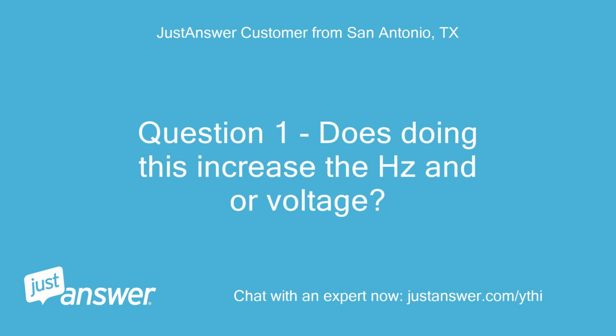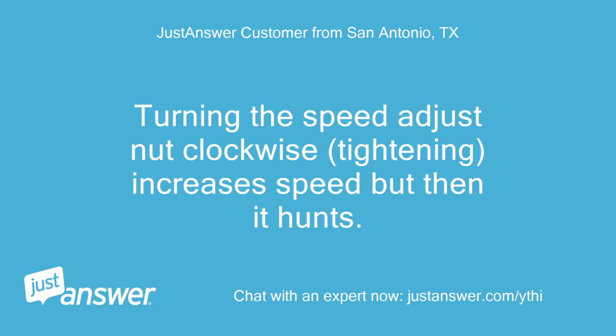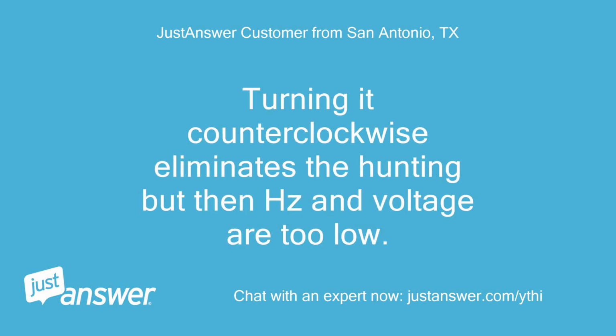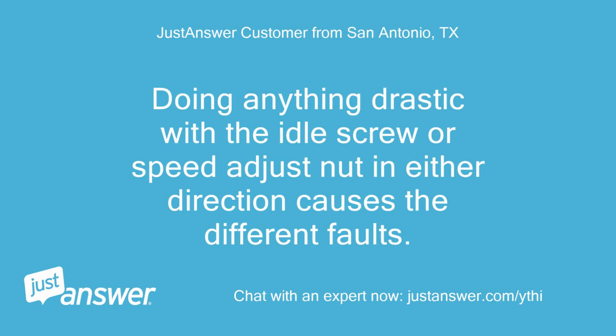Question 1. Does doing this increase the Hz and/or voltage? Turning the speed adjust nut clockwise, tightening, increases speed but then it hunts. Turning it counterclockwise eliminates the hunting but then Hz and voltage are too low. Doing anything drastic with the idle screw or speed adjust nut in either direction causes the different faults.